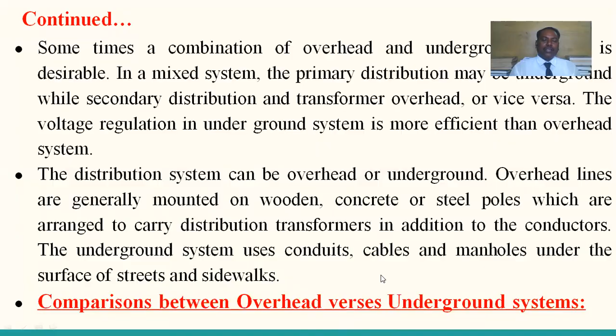These are public safety, initial cost, flexibility, faults, appearance, fault location and repairs, current carrying capacity and voltage drop, useful life, maintenance cost. Similarly, interference with communication circuit. These factors are very important for us, and how each differs between the overhead system and the underground system. So the first parameter is public safety.